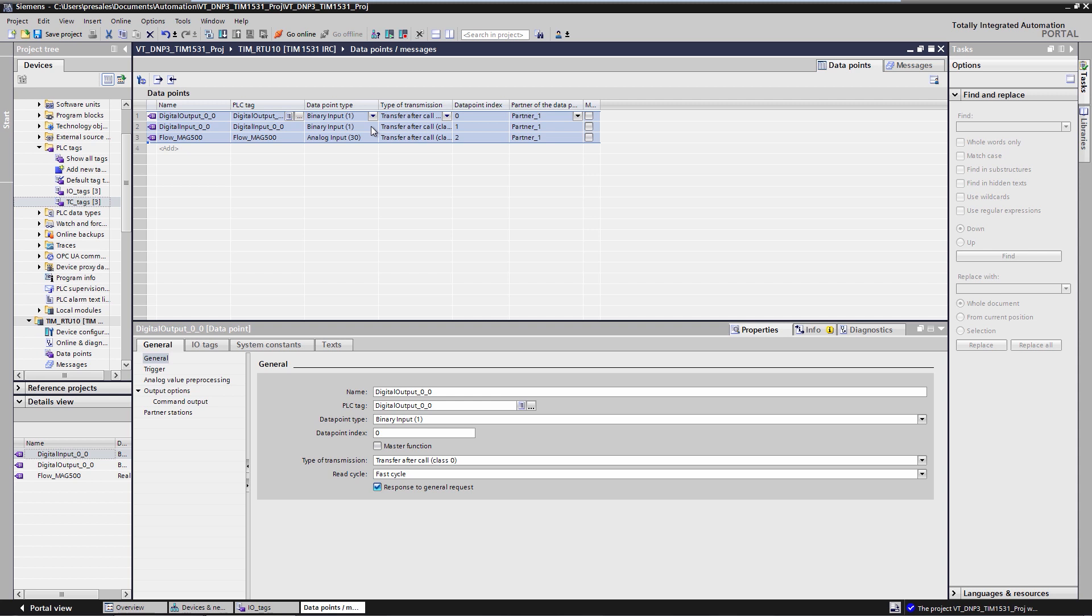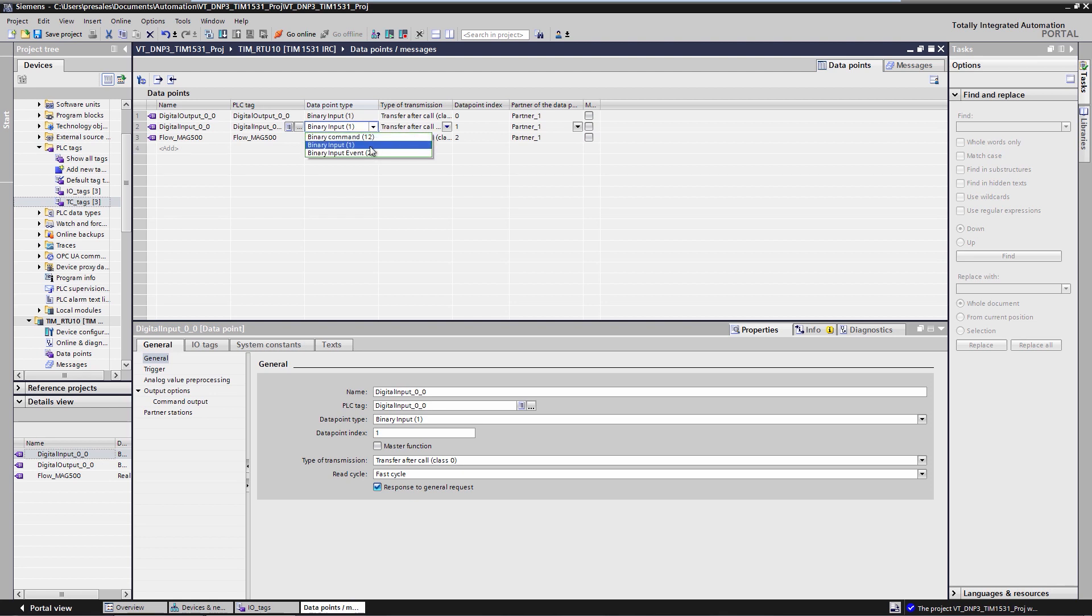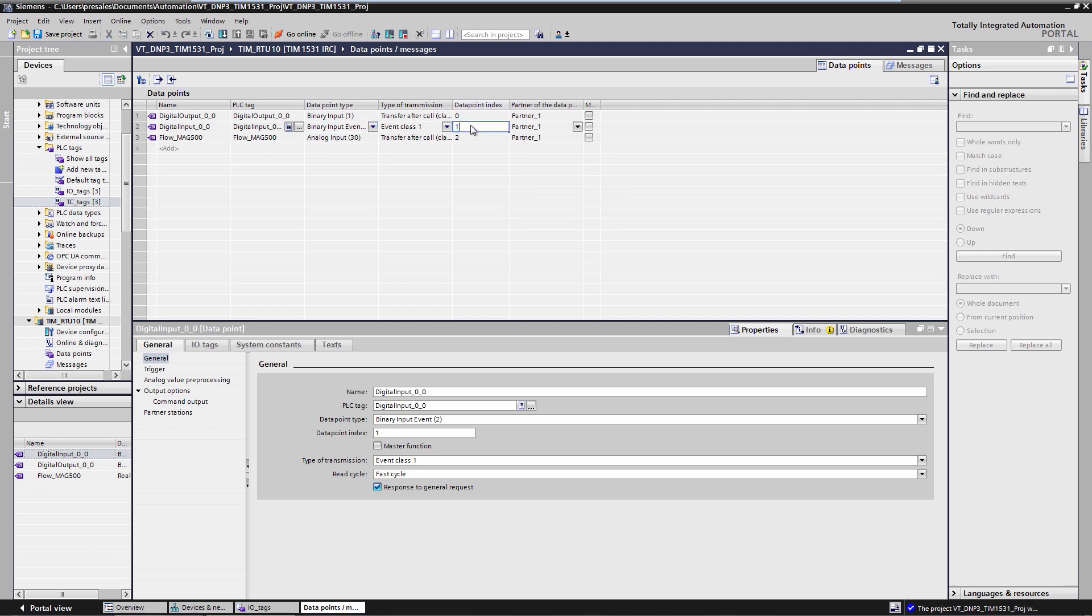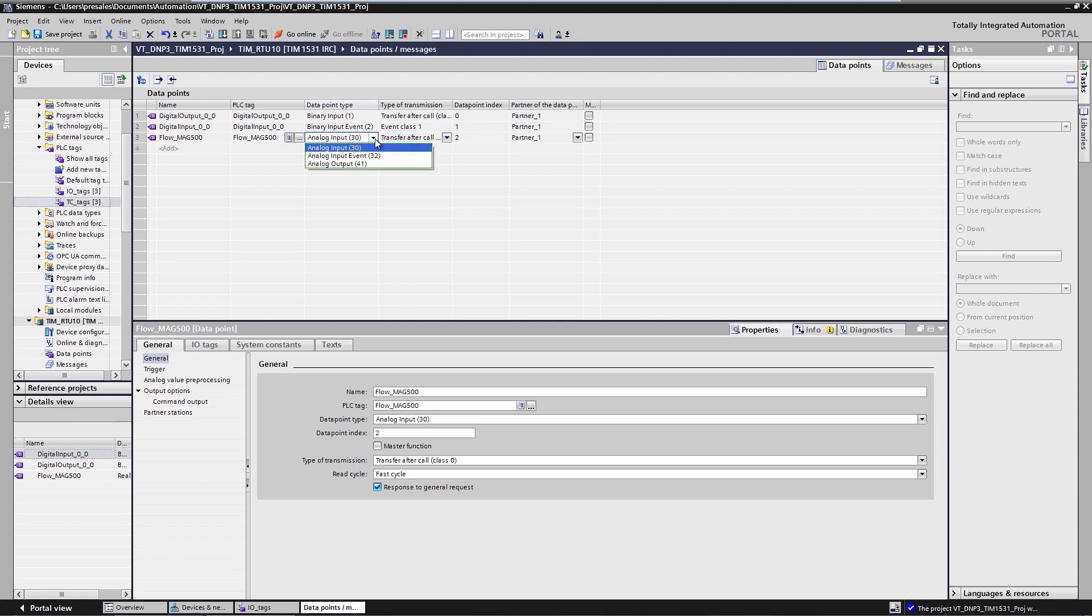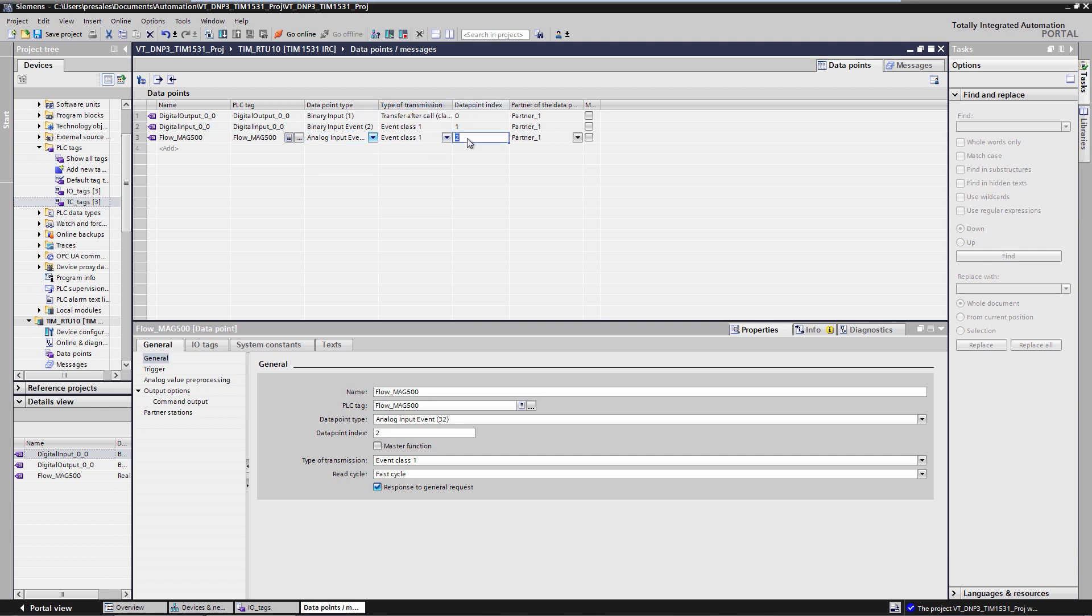I then define the DNP3 object types and the transmission parameters. According to the task, we send the alarm as an event of class 1 to the DNP3 master. The DNP3 address of the data point is index 1. According to the task, the measured value of the RTU, for example the flow rate from the MAG 5000, is also sent as an event of class 1 to the DNP3 master. Since it is a real value, object group 32 variation 7 is selected. The DNP3 address of the data point is index 5.